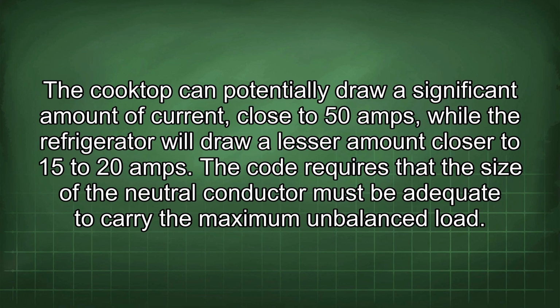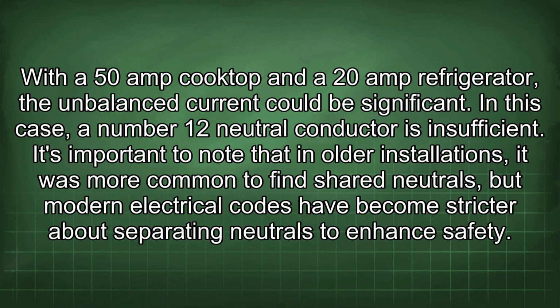The code requires that the size of the neutral conductor must be adequate to carry the maximum unbalanced load. With a 50-amp cooktop and a 20-amp refrigerator, the unbalanced current could be significant. In this case, a number 12 neutral conductor is insufficient. It's important to note that in older installations it was more common to find shared neutrals, but modern electrical codes have become stricter about separating neutrals to enhance safety.